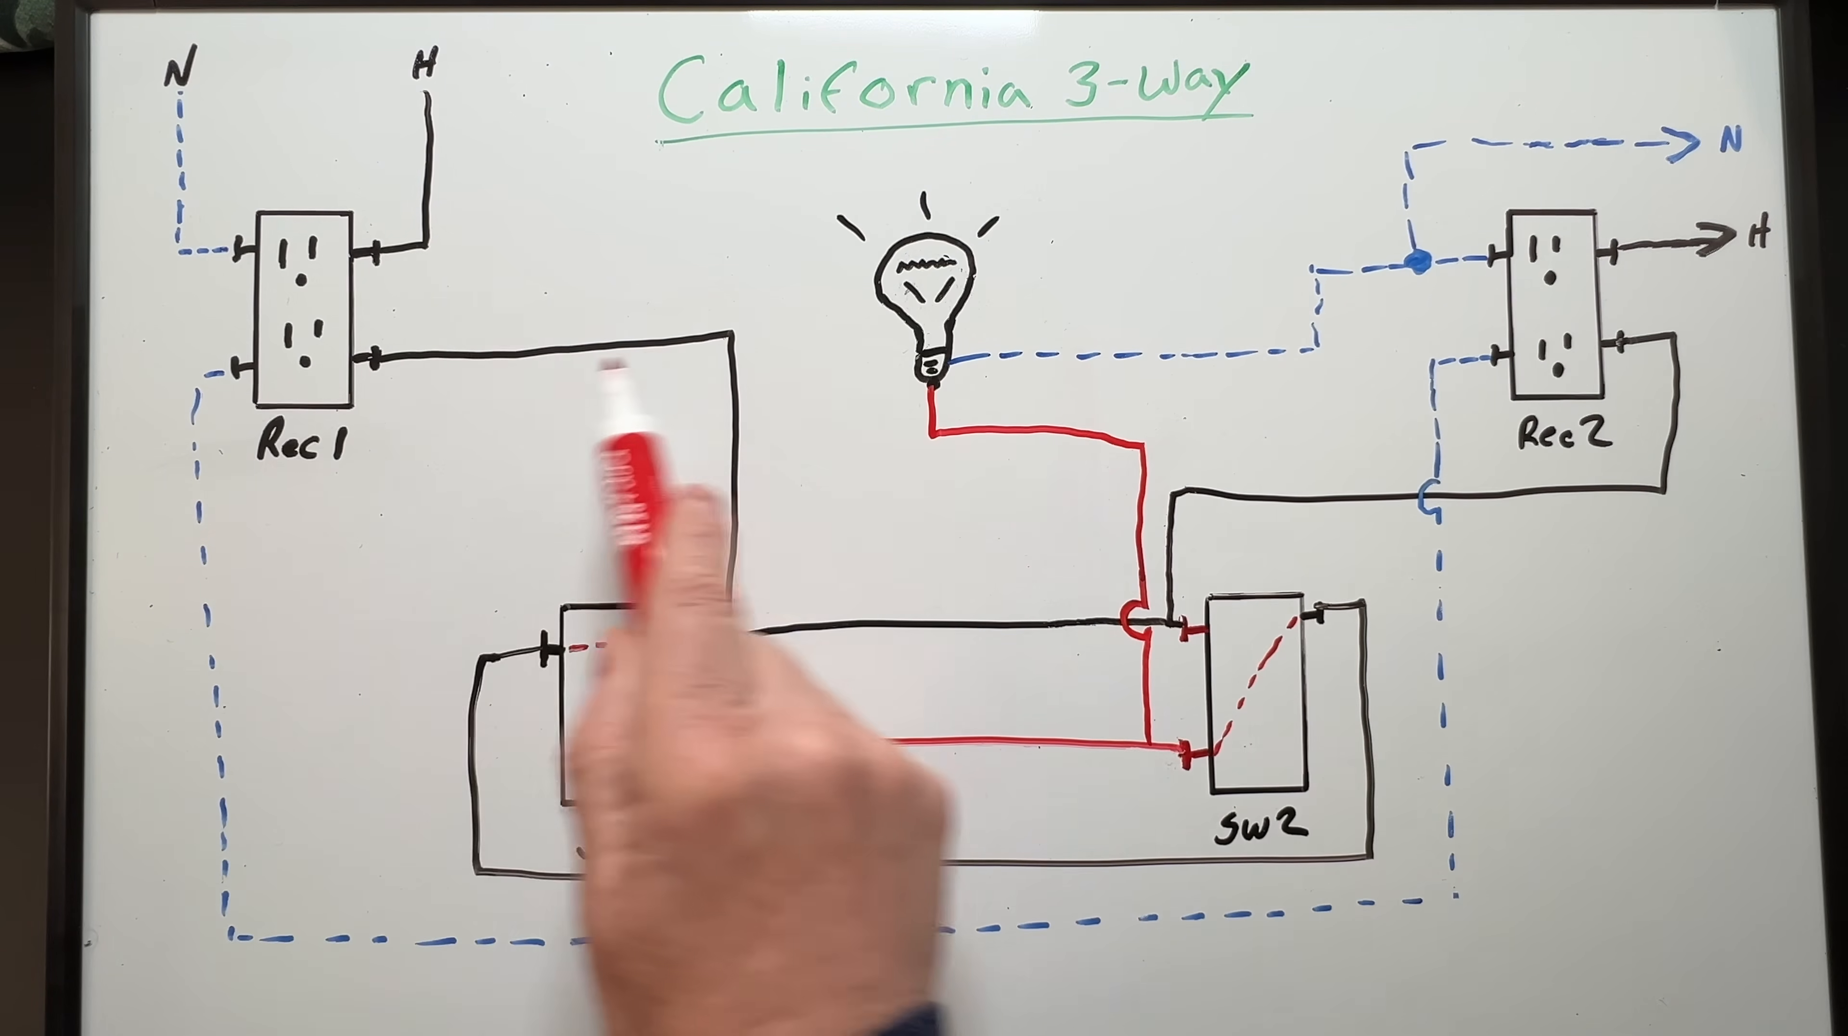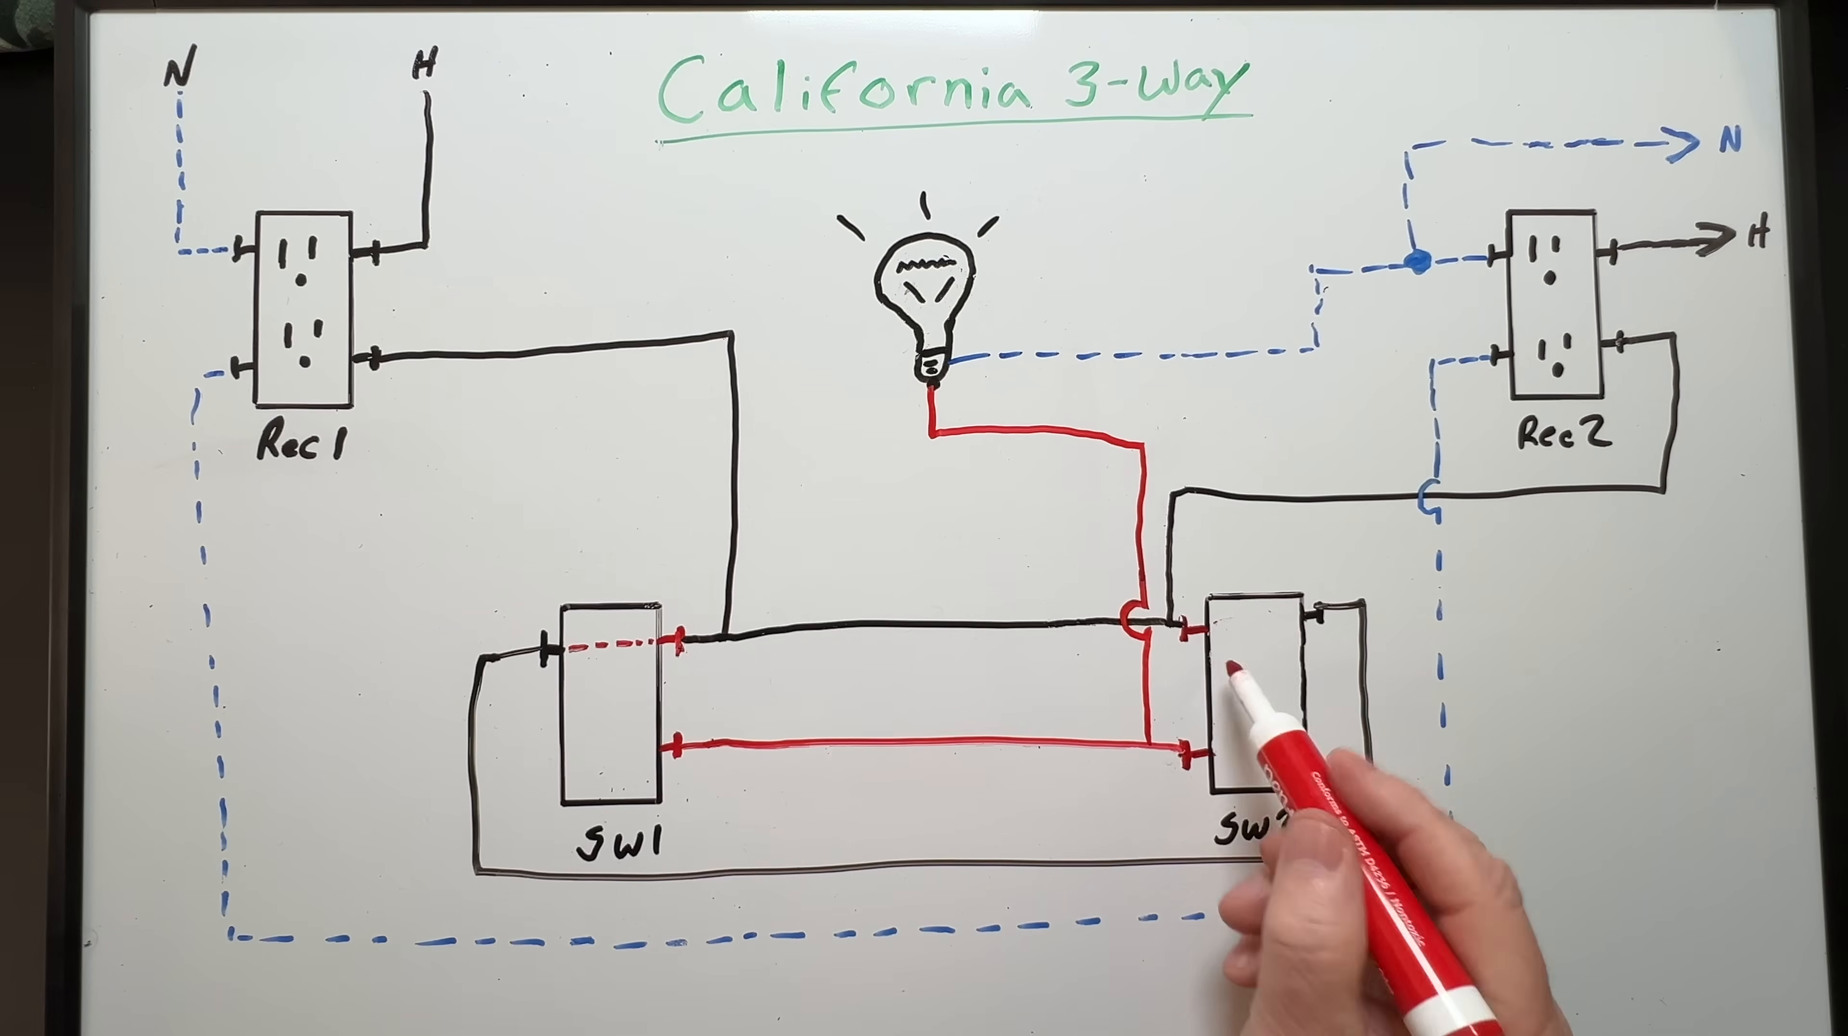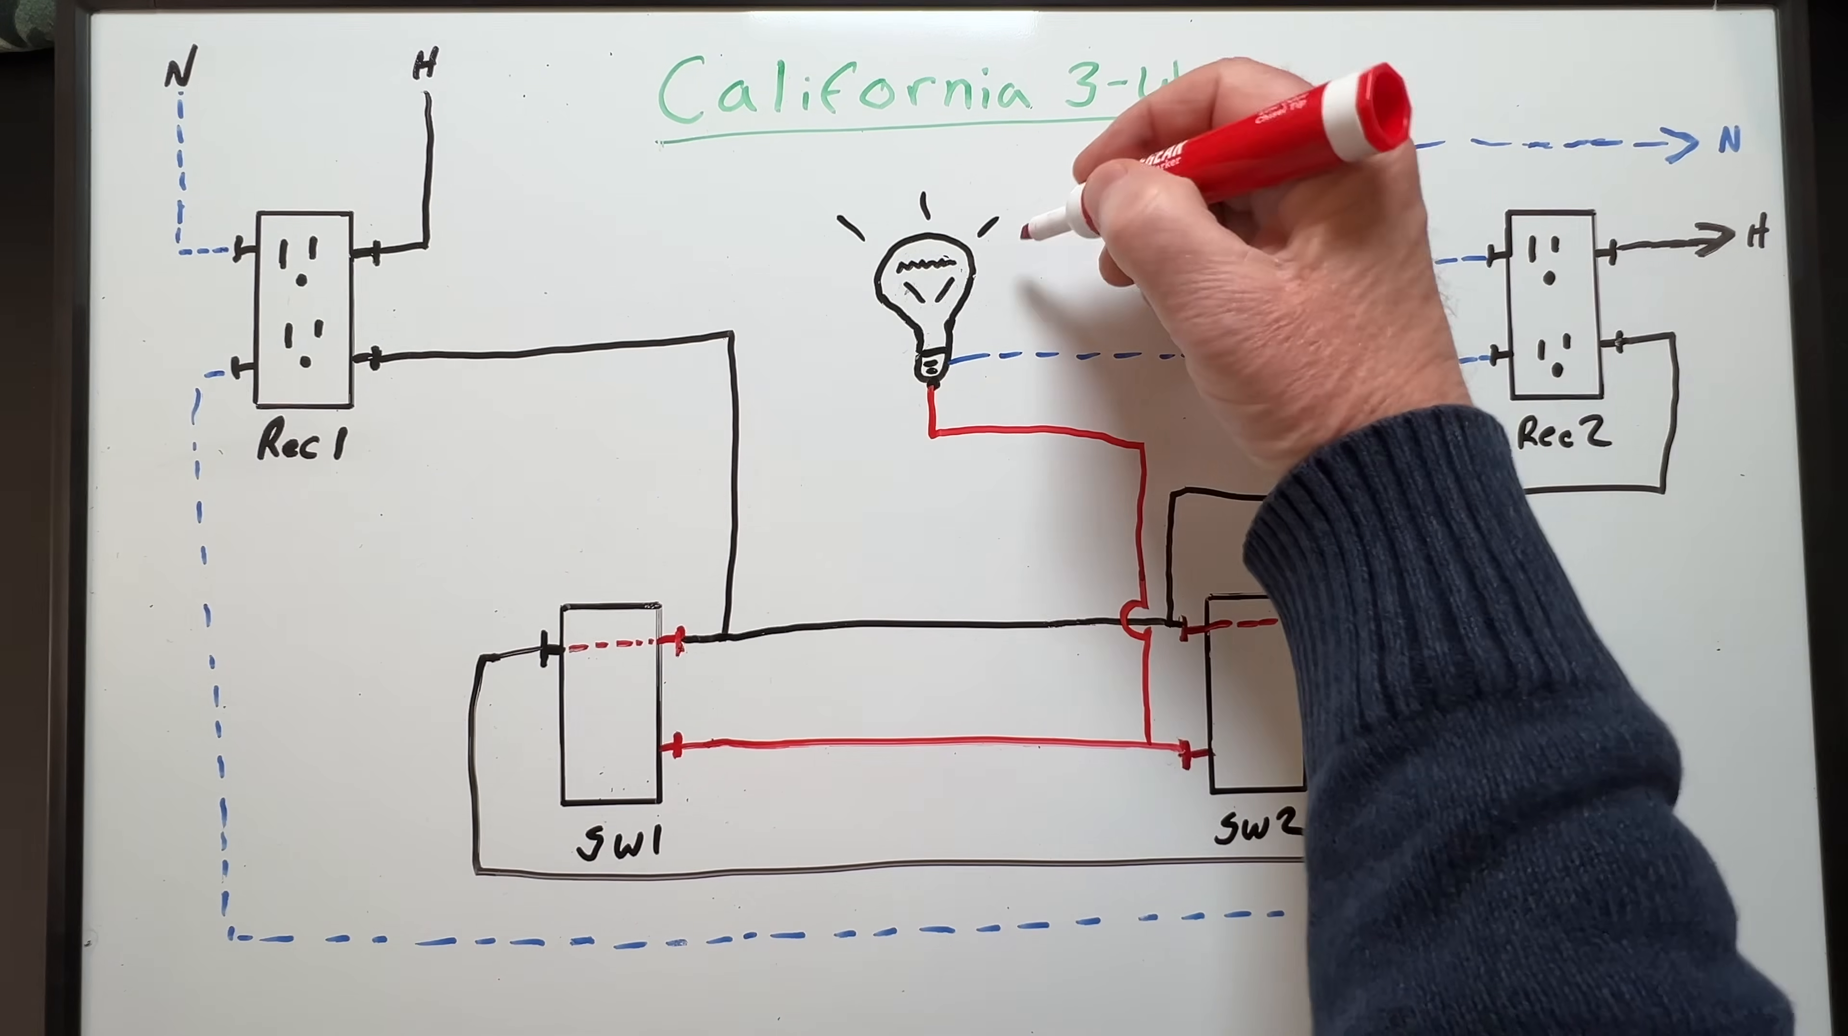So our hot wire comes down from receptacle one to switch one through switch one across the black wire over to switch two through switch two and then up to our light. Our neutral returns current back to the source so we have a complete circuit and our light will be on. Now let's move switch two to the up position. This time our power comes down from the receptacle again through switch one across to switch two through switch two and then back to switch one again so we have a loop here. The power doesn't make its way up to our light so the light will be switched off.